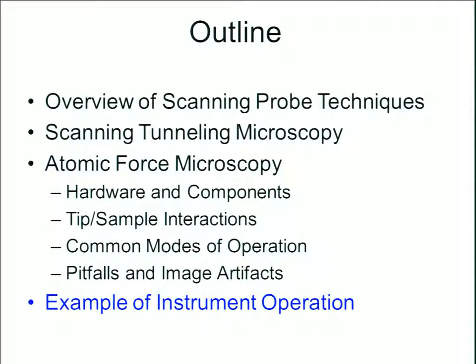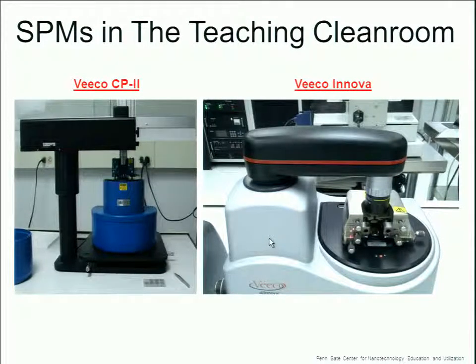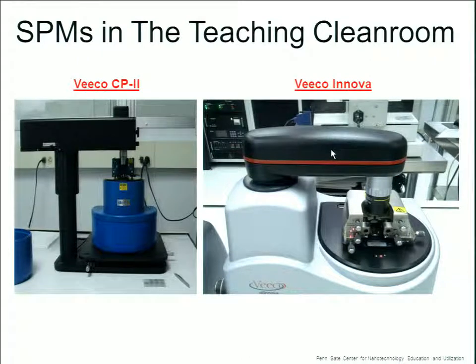As promised, we're going to show an example of using a real tool — instrument operation. Here are two examples of scanning probe microscopes: a Veeco CP2 on the left and a Veeco Innova on the right. On both, you'll see similar features. The large T-shaped structure in black is a swivel arm holding an optical microscope. The optical microscope is there solely to help us align the laser onto the cantilever, since that must be done by manual control — you manually turn the mirror to direct the laser down onto the cantilever.